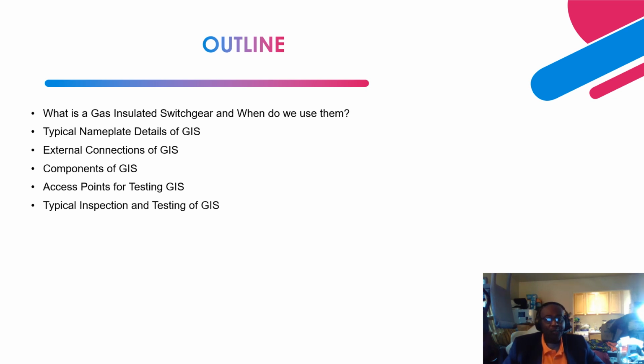Next, we'll talk about the typical inspections and testing performed for the gas insulated switchgear. Usually, each manufacturer comes up with its required inspection and testing, and most often the testing and inspections are based on the number of operations of the circuit breaker, the earth switches, and the disconnect switches. You can obtain that information from the cyclometer reading or your maintenance history of the GIS, and also the number of faults the circuit breaker has encountered.